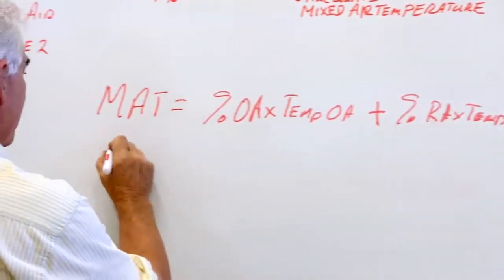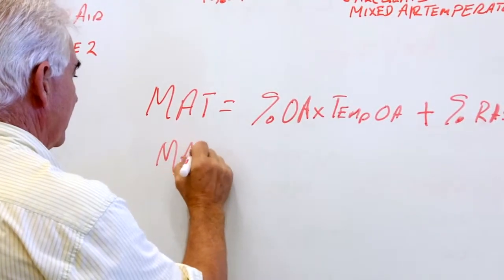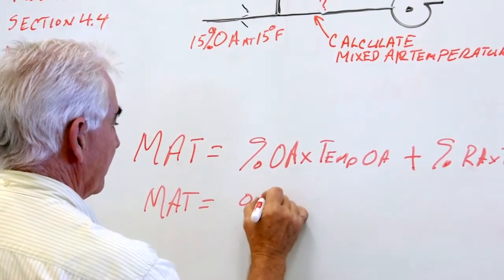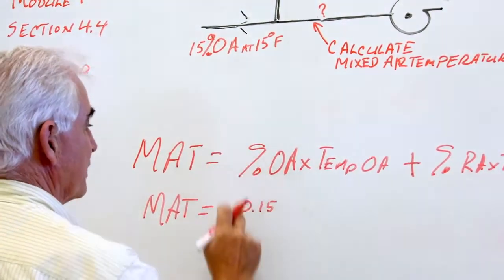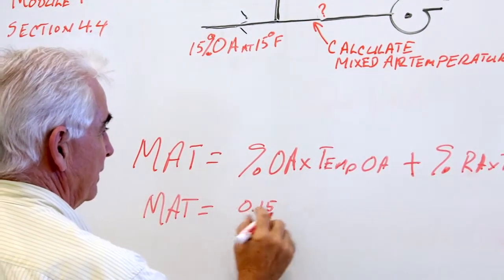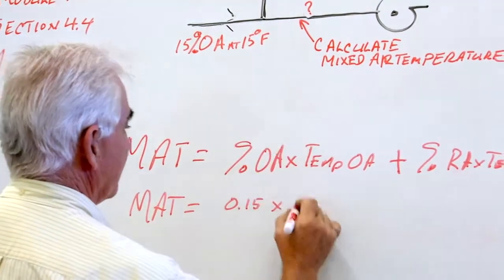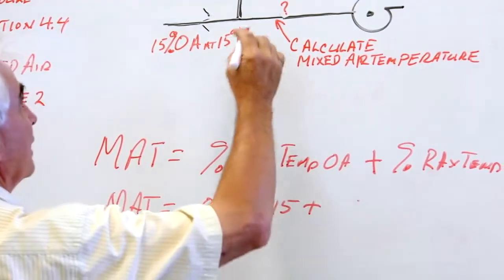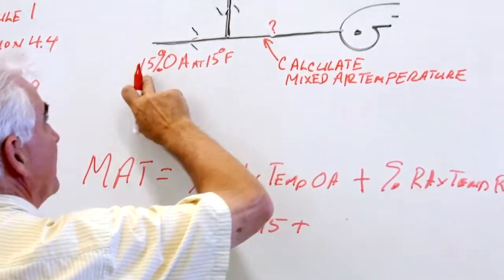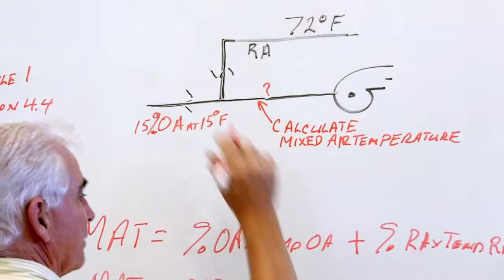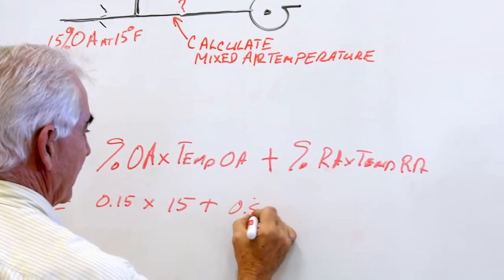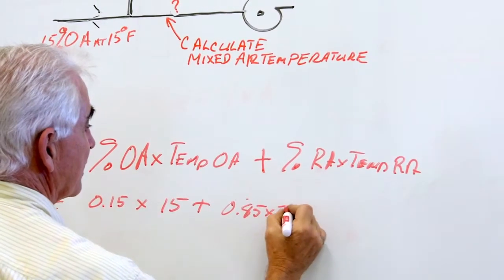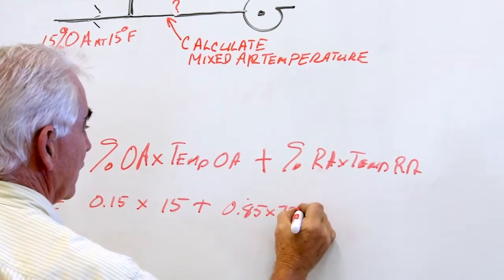To substitute, our mixed air temperature is going to be 0.15, change 15% to a decimal, times 15 degrees plus, if this is 15% then this must be 85% of the mix, we got 0.85 times 72 degrees Fahrenheit.